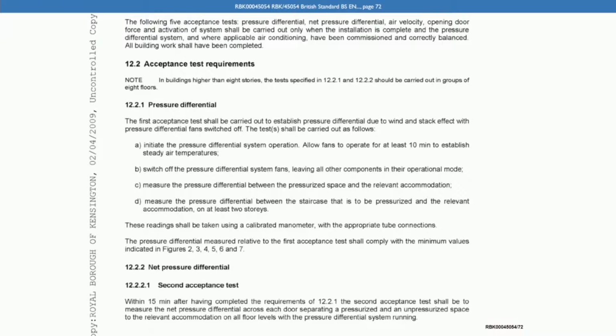So it says, initiate the pressure differential system operation, allow fans to operate for at least 10 minutes to establish steady air temperatures, switch off the pressure differential system fans, leaving all other components in their operation mode, measure the pressure differential between the pressurised space and the relevant accommodation, measure the pressure differential between the staircase that's to be pressurised and the relevant accommodation on at least 2 storeys. These readings should be taken using a calibrated manometer with the appropriate tube connectors. And then it says the pressure differential measured relative to the first acceptance test shall comply with the minimum values indicated in figures 2, 3, 4, 5, 6 and 7. Now, was this a process that you followed? Did you run the system's fans for 10 minutes and then take those test measurements with the fans on?